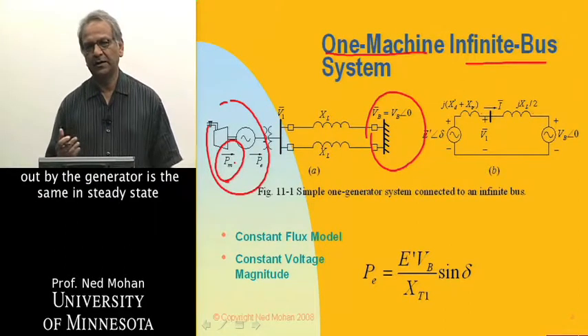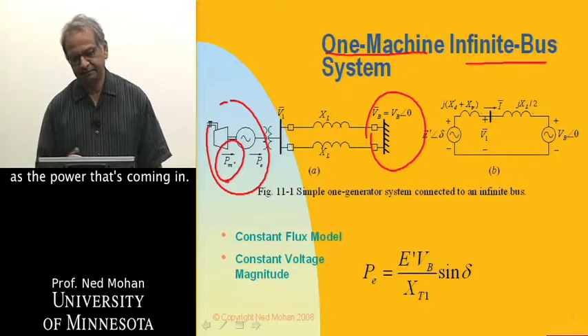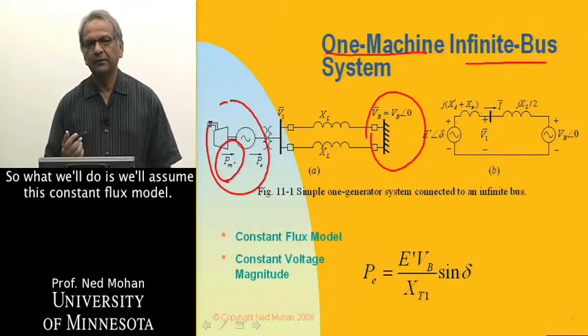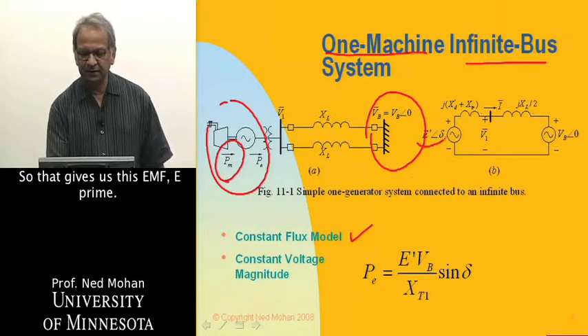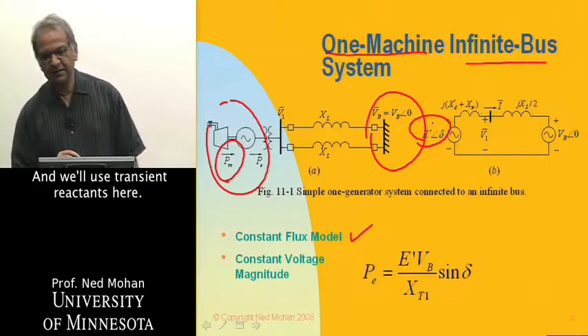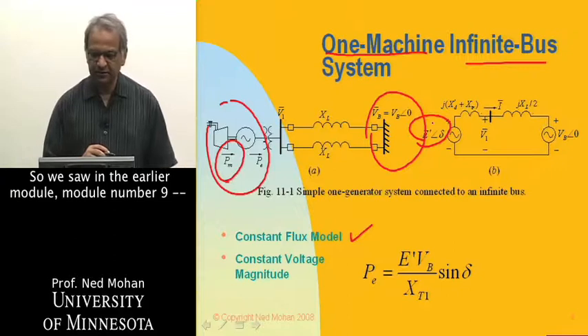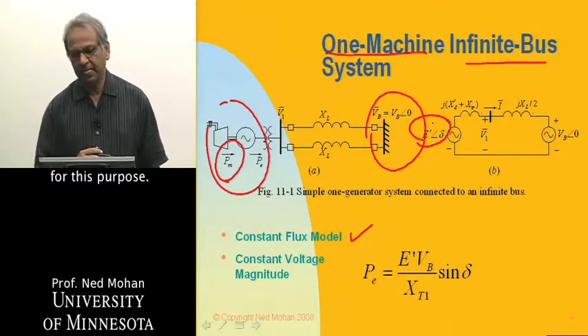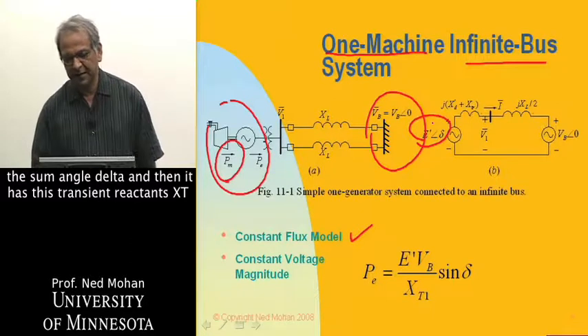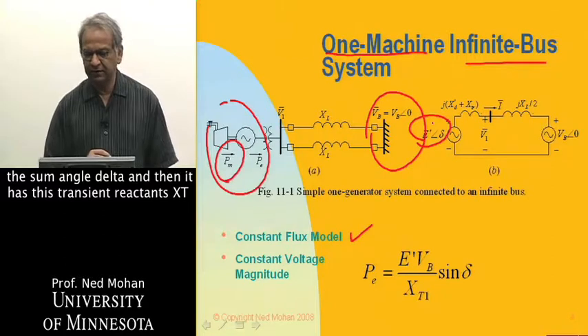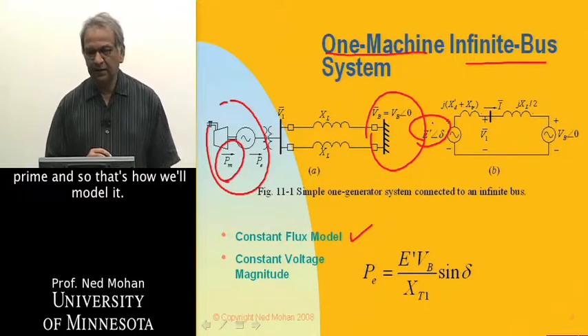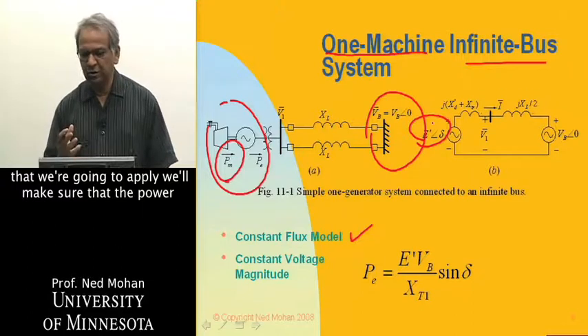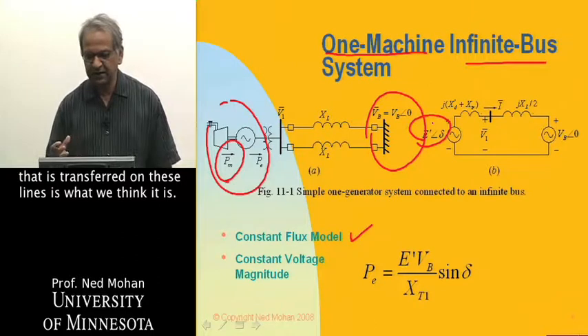To model the generator for this study, we use a constant flux model, giving an EMF E' with transient reactance X'T — as discussed in module eight. We model it as this back EMF E' at angle delta, in series with transient reactance X'T. In steady state, prior to the fault, we ensure that the power being transferred on these lines is correct by modeling it with synchronous reactance and the back EMF. We also assume the study duration is short enough that the exciter doesn't have time to change the EMF, so E' is constant in magnitude, though the angle delta will oscillate.